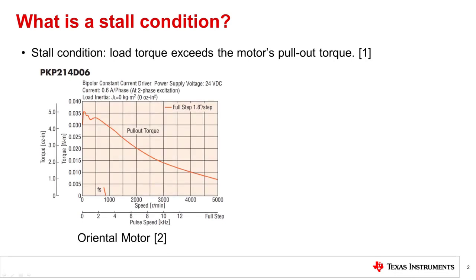Motor manufacturers will provide torque or pullout curves similar to the one shown here. This curve shows the motor's pullout torque for a range of speeds, and the pullout curve profile will be different from motor to motor. Designers use this curve to ensure that the motor's torque capability can meet the mechanical torque requirement of the system. The pullout torque decreases as the speed increases and is also proportional to the motor current, so the pullout torque curve will be specified for a particular motor current.